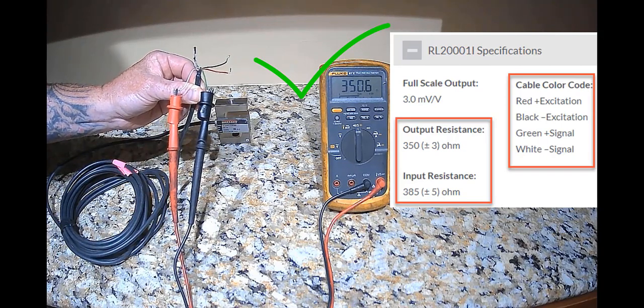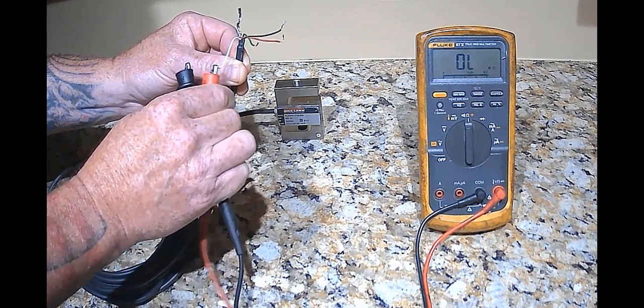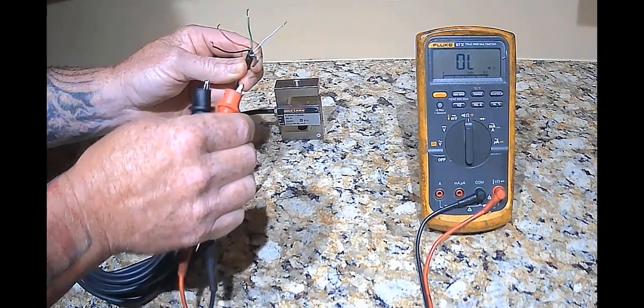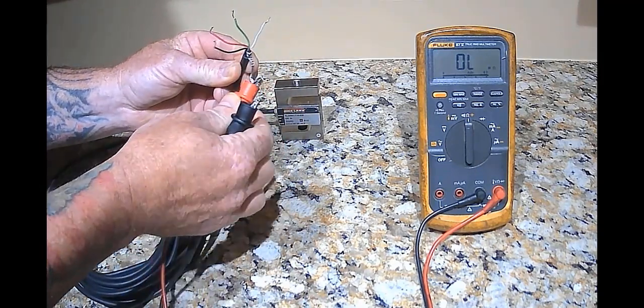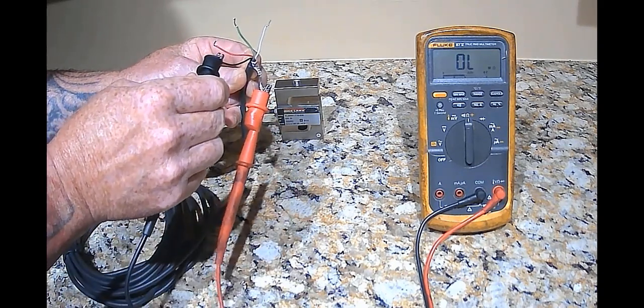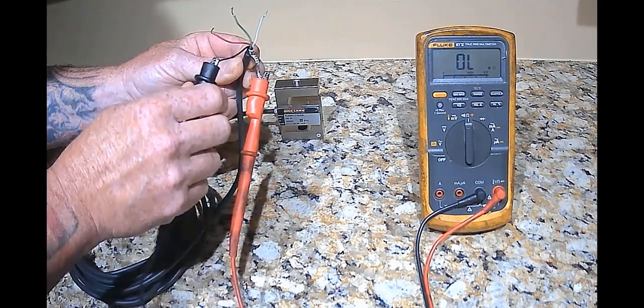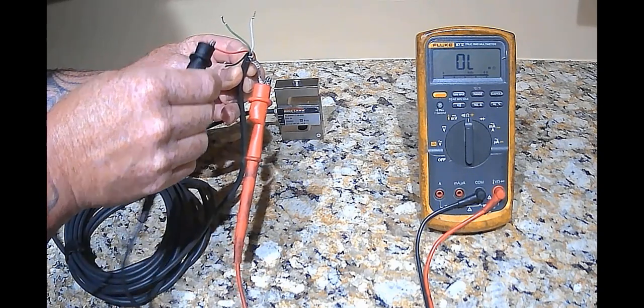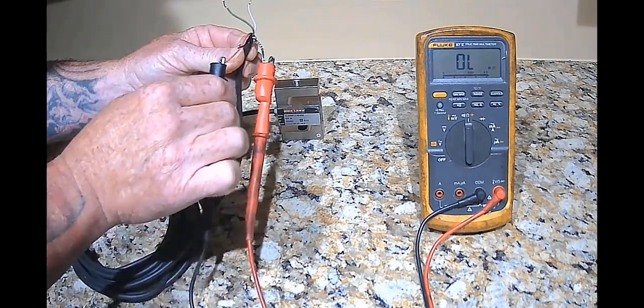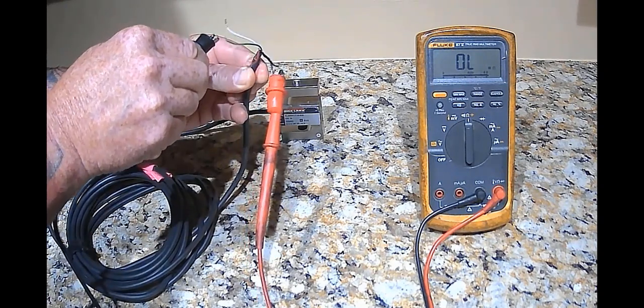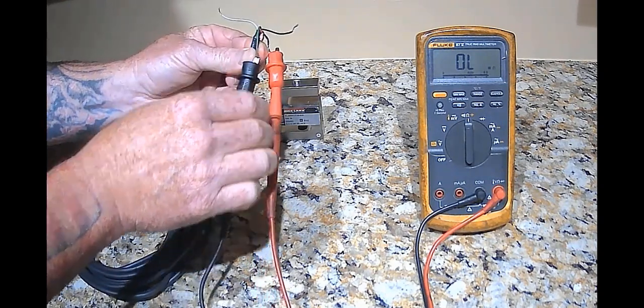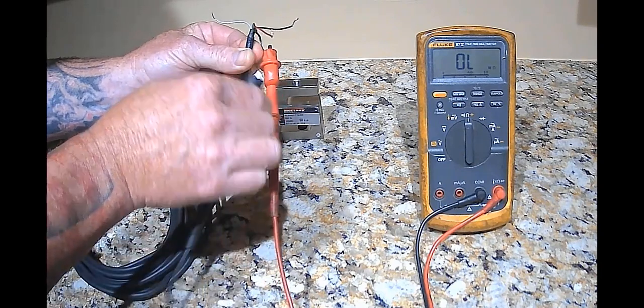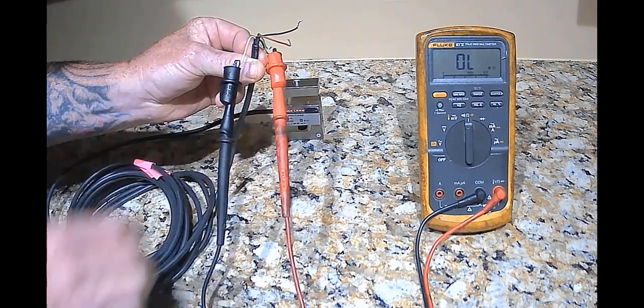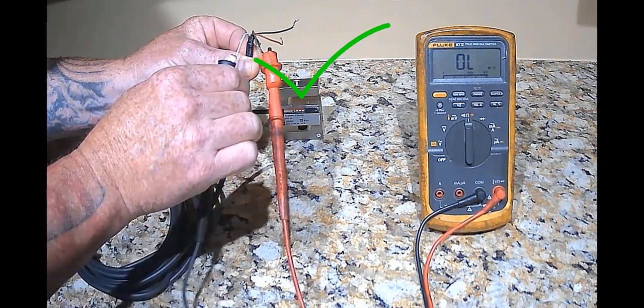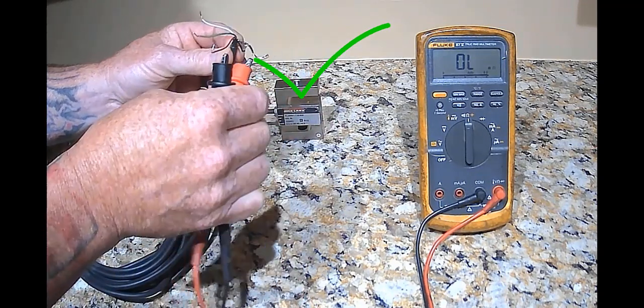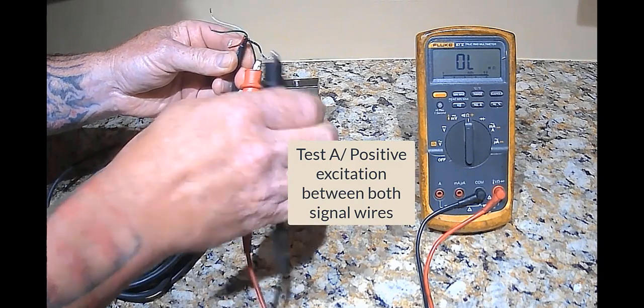Next, connect a lead to the shield wire, then take the other probe and go to each input and output wire. The reading should be OL. If any other reading, then it is leaking to the shield and the cell should be replaced. Even if the overall output resistance test was within normal specification, the load cell could still be damaged.